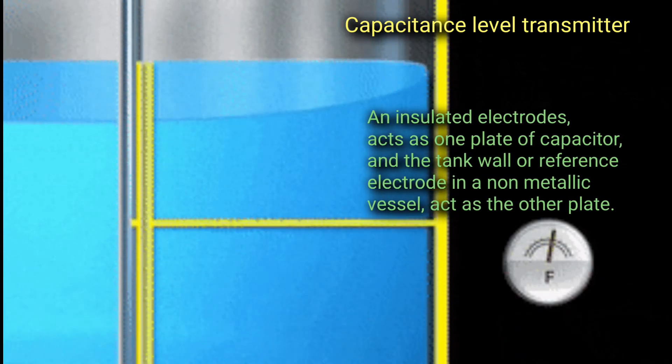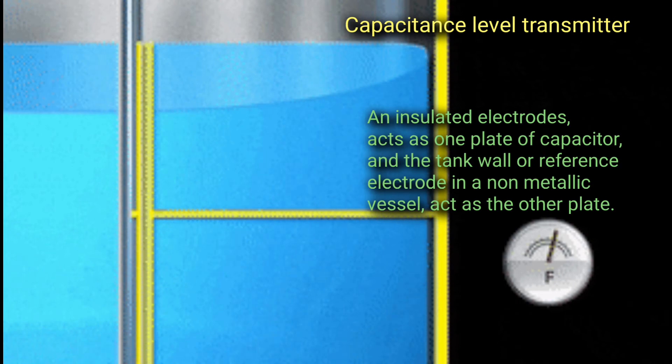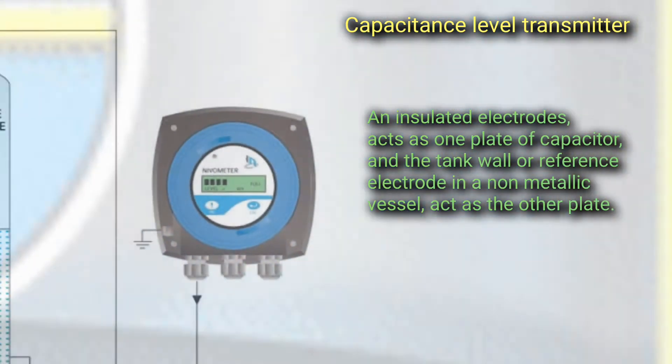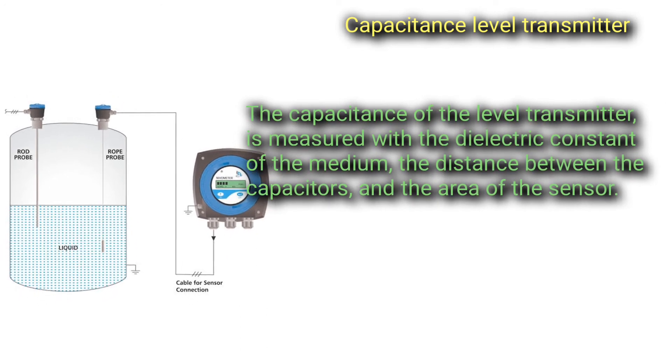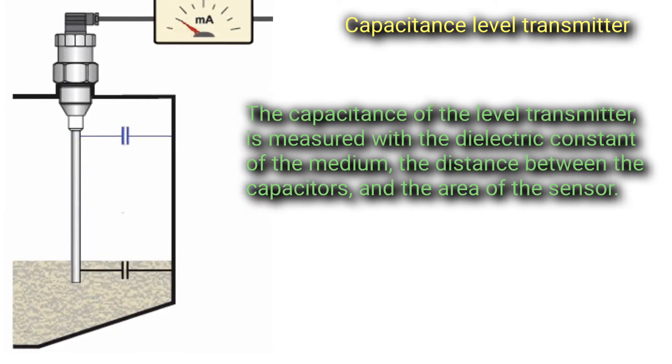An insulated electrode acts as one plate of the capacitor, and the tank wall or reference electrode in a non-metallic vessel acts as the other plate.